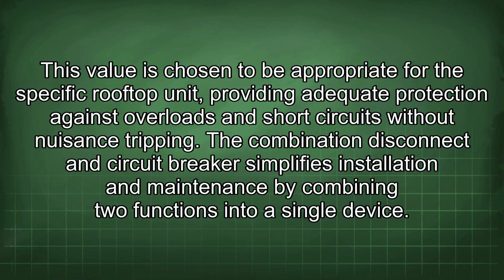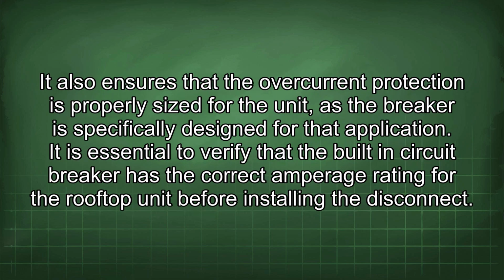The combination disconnect and circuit breaker simplifies installation and maintenance by combining two functions into a single device. It also ensures that the overcurrent protection is properly sized for the unit, as the breaker is specifically designed for that application. It is essential to verify that the built-in circuit breaker has the correct amperage rating for the rooftop unit before installing the disconnect.